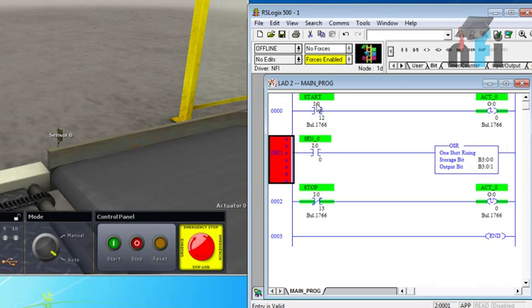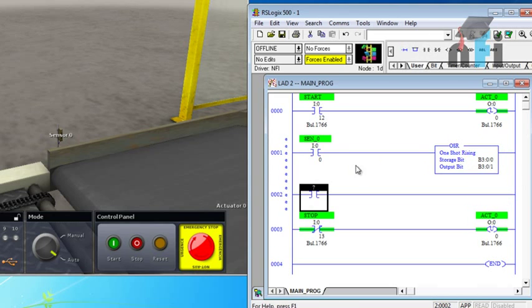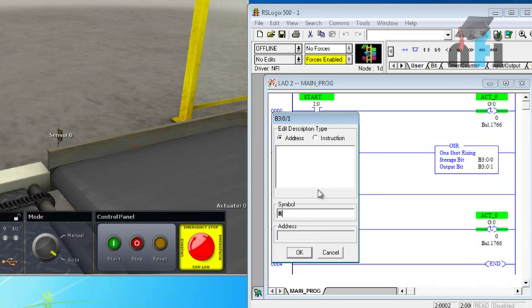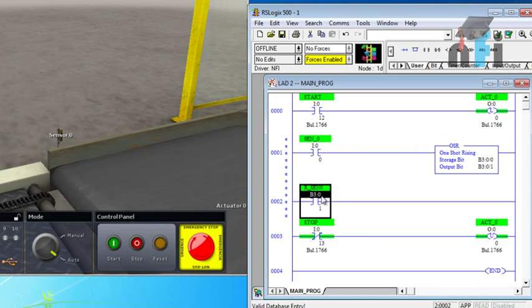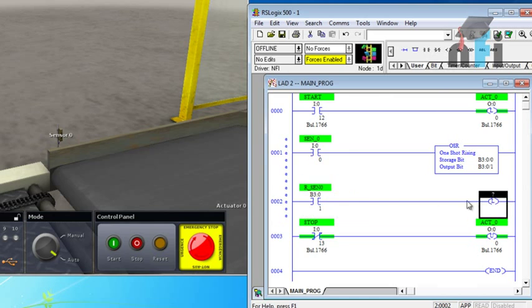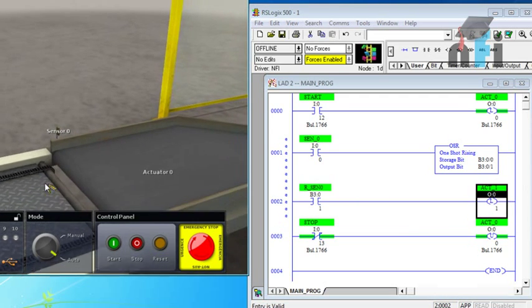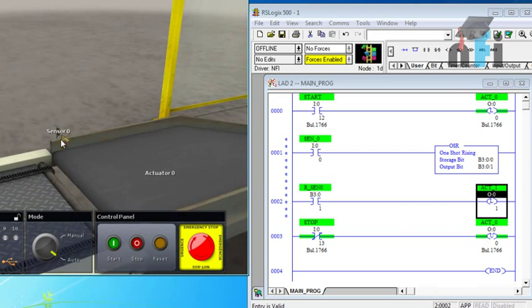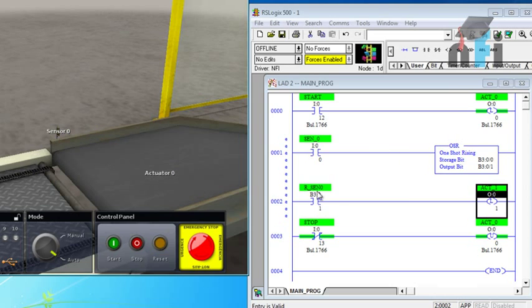Take one more contact and drag it over. This becomes the rising edge of sensor zero - R sensor zero. Using that rising edge we have to latch the output, so use latch and give it address O colon zero slash one. So the rising edge of sensor zero will latch actuator one. Now, when the box leaves sensor zero - that is the falling edge - actuator zero should be off.